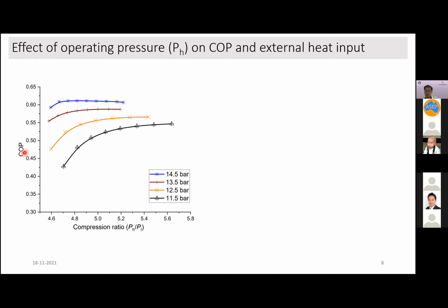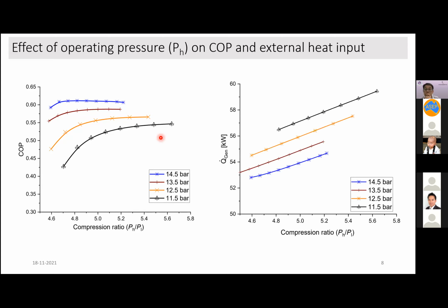This is the variation of COP in relation to the compression ratio at a certain operating pressure. It can be observed that with increasing compression ratio the system COP increases, and also with increasing higher pressure. Let's say pH equals 14.5 bar, the system has the highest COP, and at pH equals 11.5 bar, the system has the lowest COP. This is because as the operating pressure lowers, the heat required by the generator increases, as can be seen here. At the higher operating pressure, that is pH equals 14.5 bar, the system has the lowest requirement for external heat, that is Q dot gen. And as the pressure decreases, the external heat requirement increases.